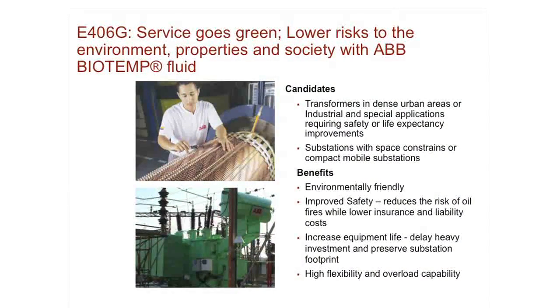Candidates for Biotemp: dense urban areas, indoor transformers that have high fire risk or high risk of failure that would create a catastrophic failure or a fire. Substations with space constraints where they're around or in proximity to critical transformers, such as GSUs, or in a plant facility, as I said, inside of a building for site power or such.